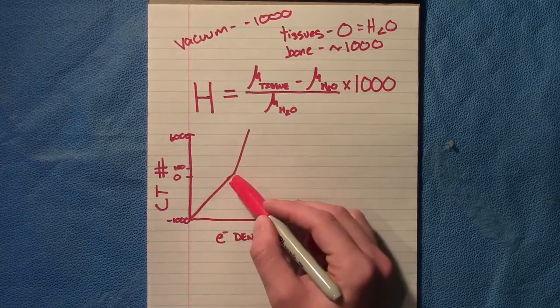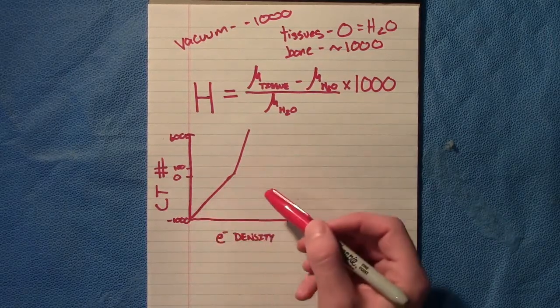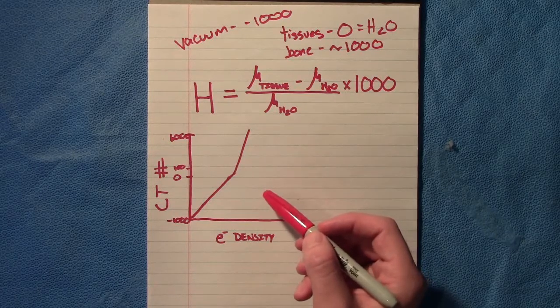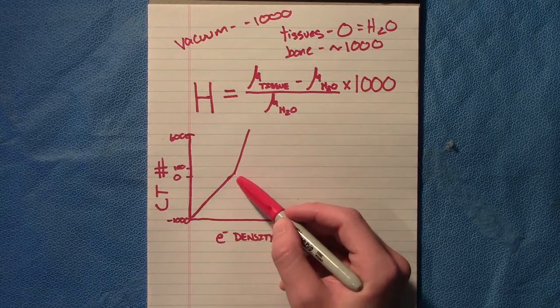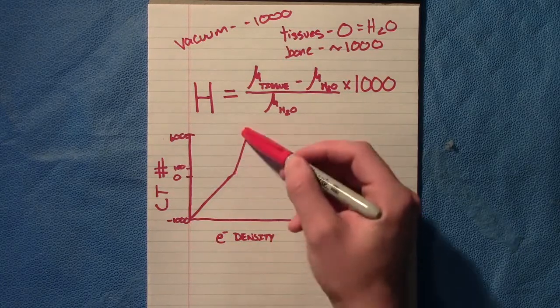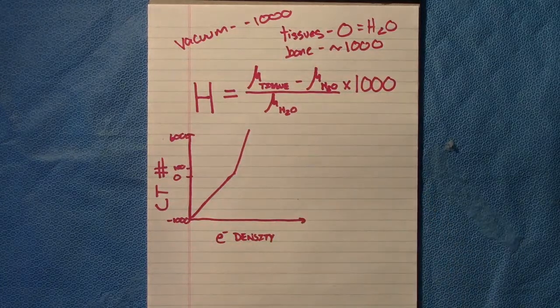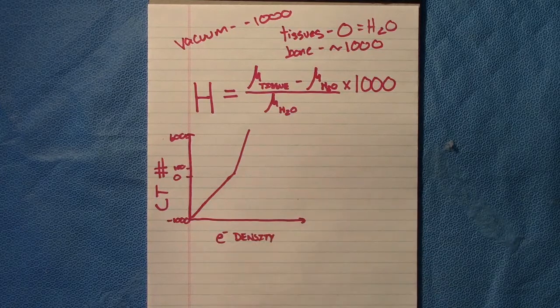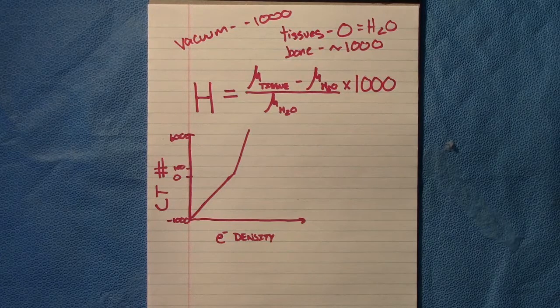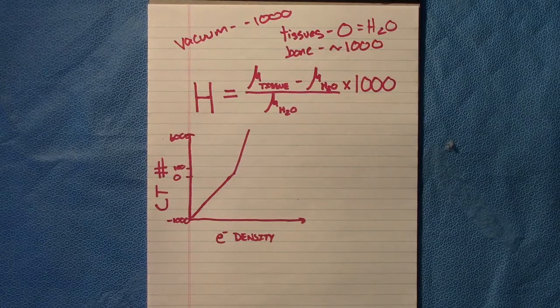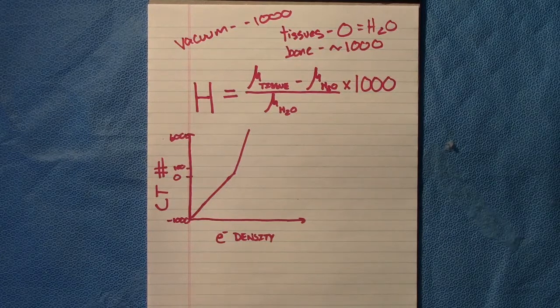But there's a point in all of your electron density curves where that linear portion is going to trend upward. It's no longer going to be linear; it's going to look something similar to this. And that is because the atomic number in the tissues changes and causes that non-linearity.